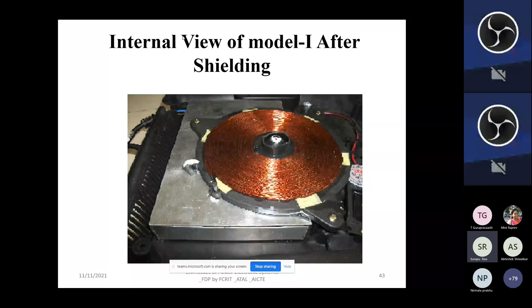But since this is an electrical induction cooktop, nothing has happened to this, because its function is only to heat the equipment, heat the particular thing. So radiated susceptibility is not much of a concern for this equipment. Similarly, conducted susceptibility, yes, we also tested that, and we tried to launch spikes of 100 volt and 1 microsecond duration through the cable. But inside there is already protection by surge arresters and metal oxide varistors on the PCB, so that will take care of these transients and surges. So there was not much concern about radiated and conducted susceptibility. But the concern was radiated emission and conducted emission. That part we have already shown you.